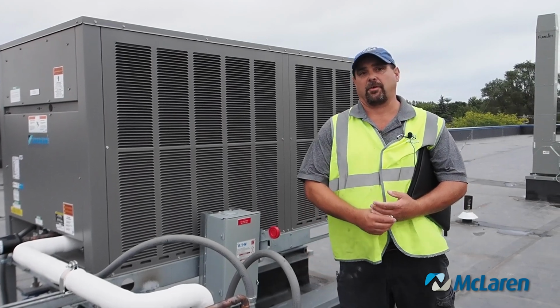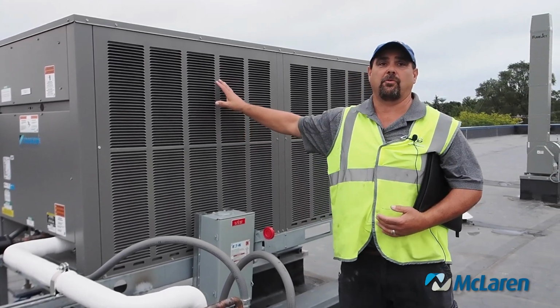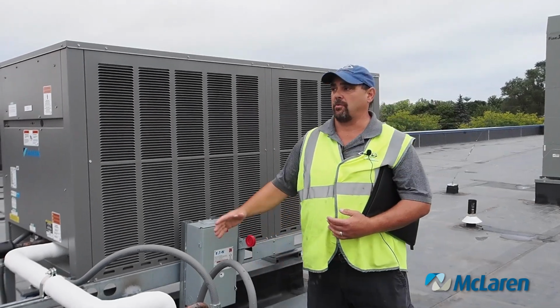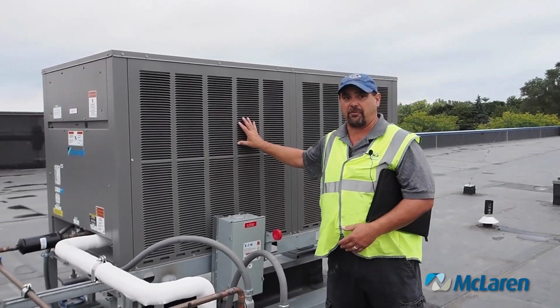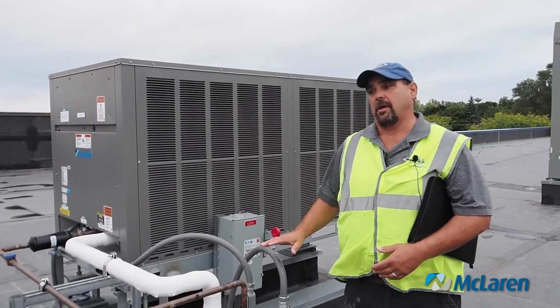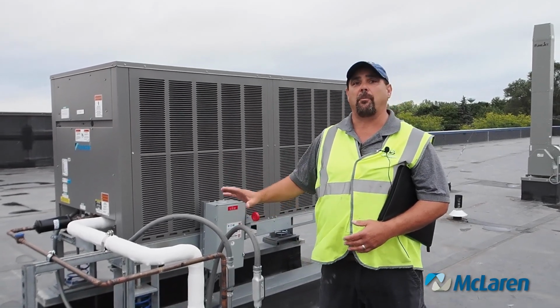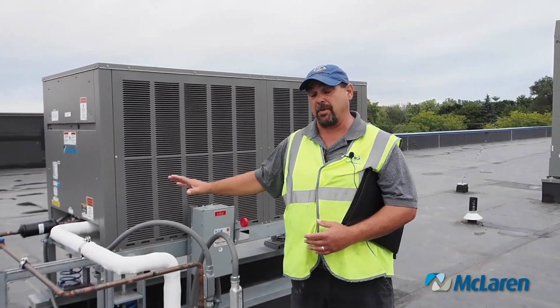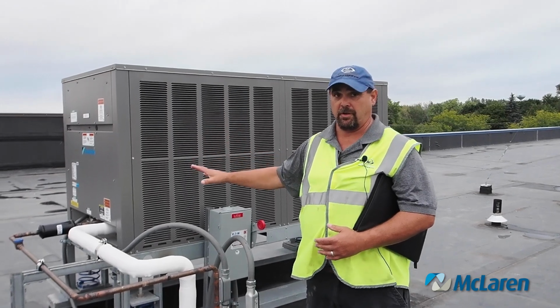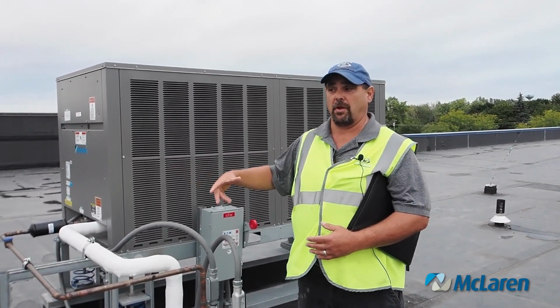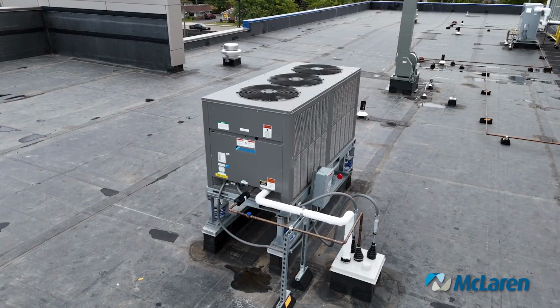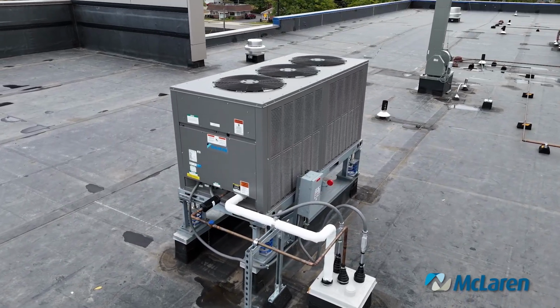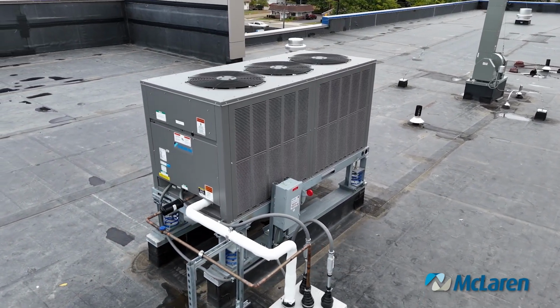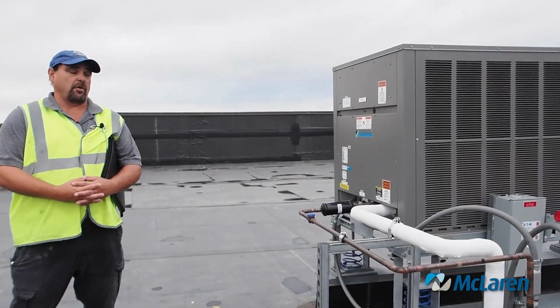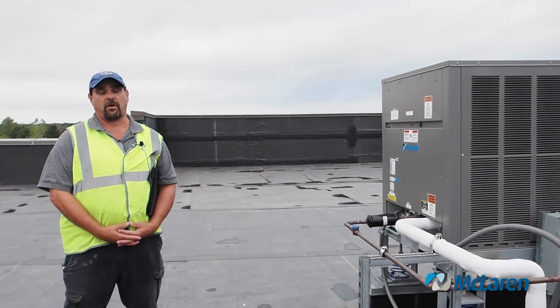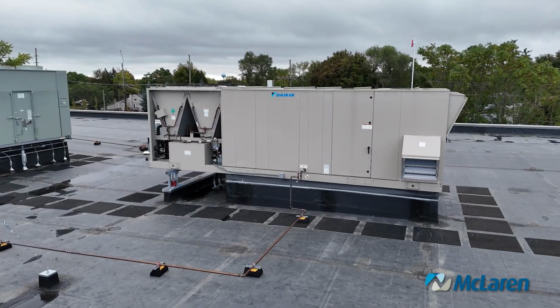I can't tell you that, because this might be in a Sierra desert where no trees are around. This might be cottonwood. I don't know the environment to know how often this is going to require a cleaning. That is 100% visual. There's no BMS to measure that. The BMS will show you the result of a bad or dirty coil. It'll shut off on high pressure and the BMS will get an alarm. That's when you first come up here and check if it's clean or not and the condenser fans are operating. Yeah, so I cannot tell you how often to clean it. It is 100% visual inspection.